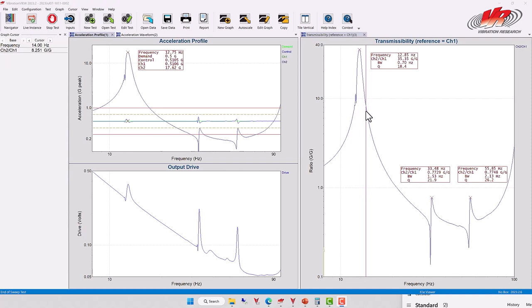And the half power in the vibration industry is represented by plus or minus 3 dB, which corresponds to 70.7% of the amplitude value. A plus or minus 3 dB value in power is equivalent to taking the acceleration amplitude and dividing by the square root of 2, or in other words, multiplying by 0.707.